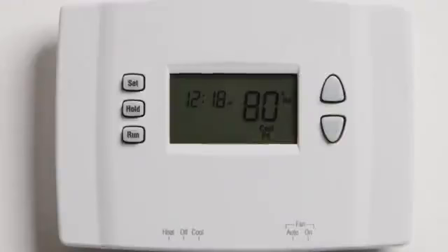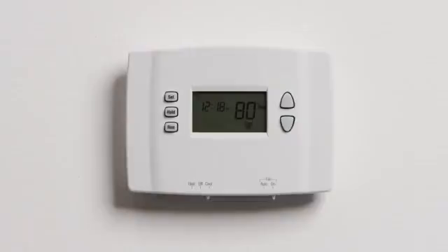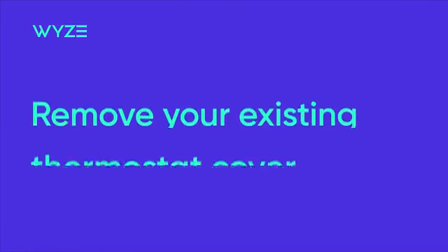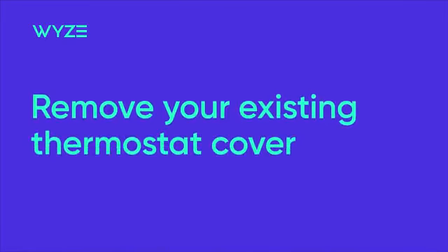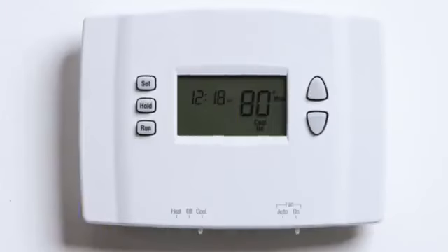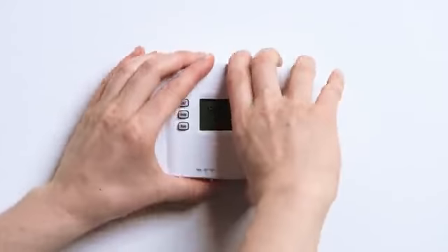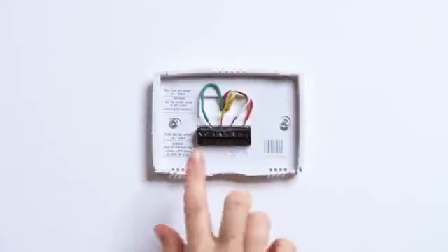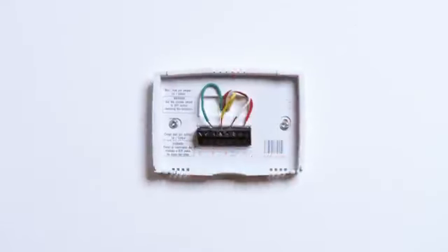Note that some thermostats have a battery built in, so the screen may stay on even if the system power is off. You can check to ensure the power is off by changing the temperature and then waiting for a few minutes to make sure your system doesn't turn on. Once the system is powered off, remove any screws holding the cover to the wall and remove the display. Many models without screws simply pop off. You should now see wires coming from your wall into the thermostat's terminals.